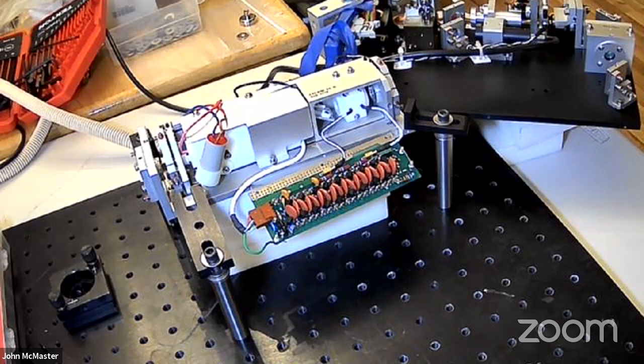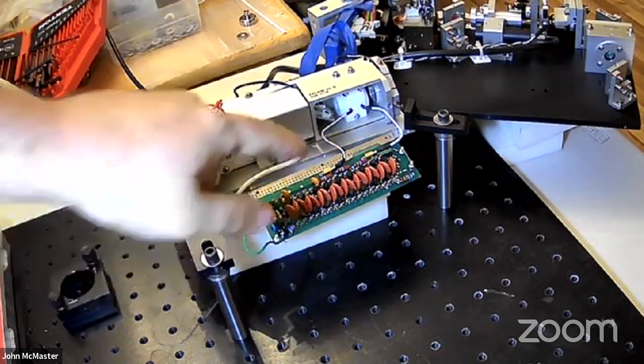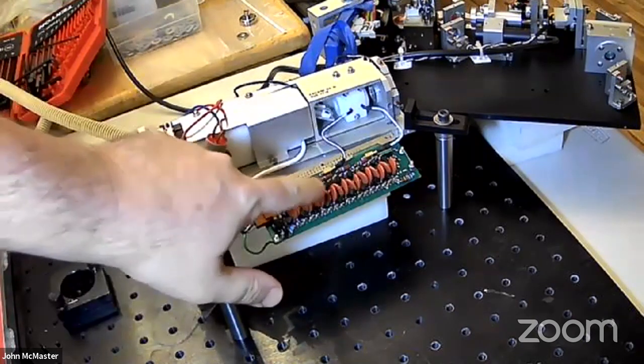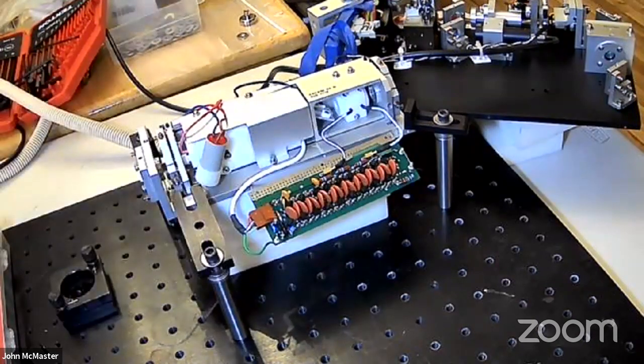So it's almost like a capacitor. Think of it like an optical capacitor. It just keeps building up energy. At some point, though, we're going to apply a high voltage pulse, which is delivered by this board here. And that's basically going to turn this optical switch on, and then it's going to dump an extremely fast, very high power laser pulse out the side of the laser over here. Does that make sense so far?